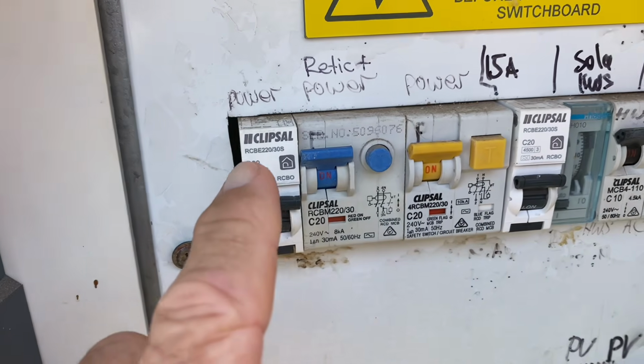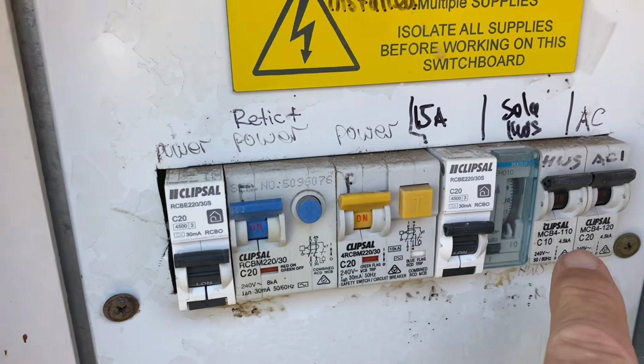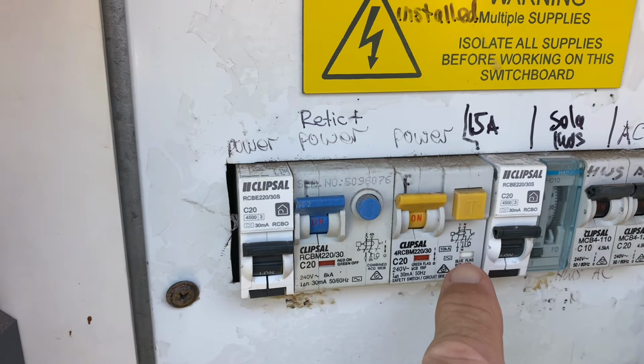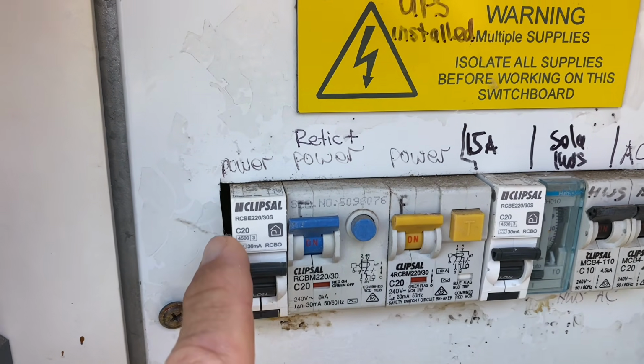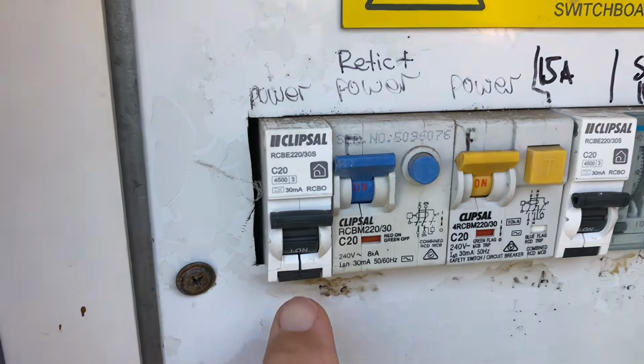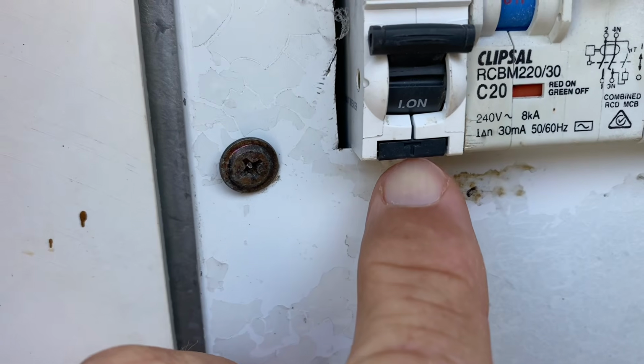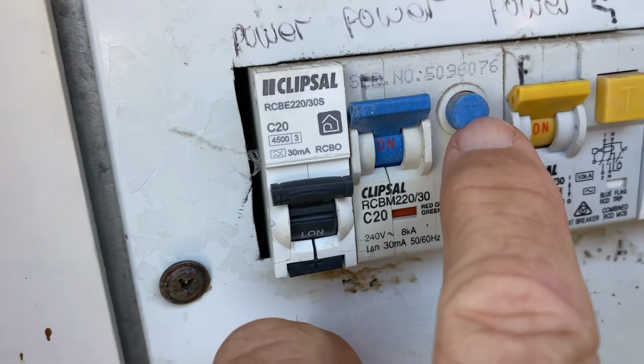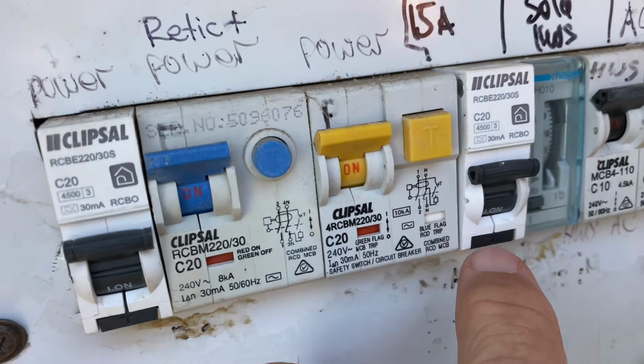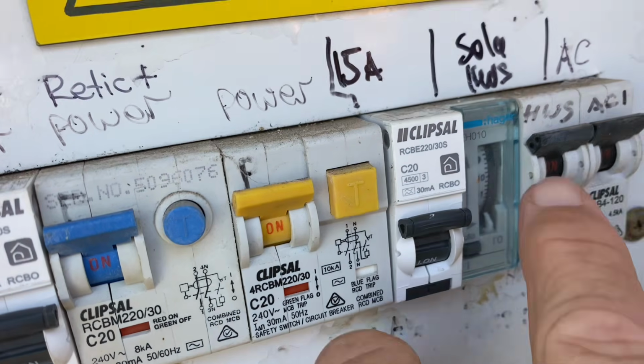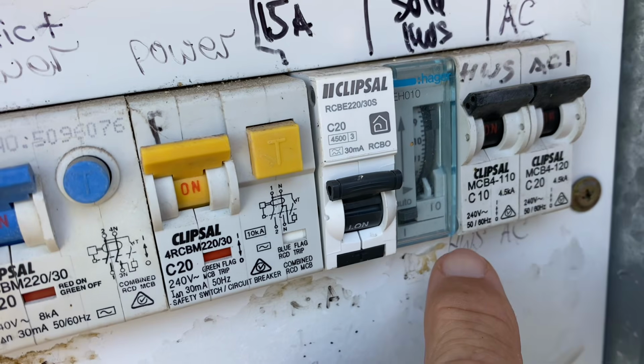Just how you can identify an RCD from a regular circuit breaker is an RCD or RCBO will always have a test button. So that's a test button, that's a test button, that's a test button. You'll notice on these ones there is no test button.